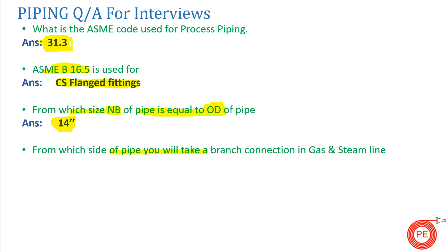The next question is: from which side of the pipe do you take a branch connection in a gas and steam line? The answer is from the top side. This applies to gas and steam lines. However, if someone asks from which side you take the connection for a water line, the answer is the bottom side. So for gas and steam it is top side, and for water it is bottom side.